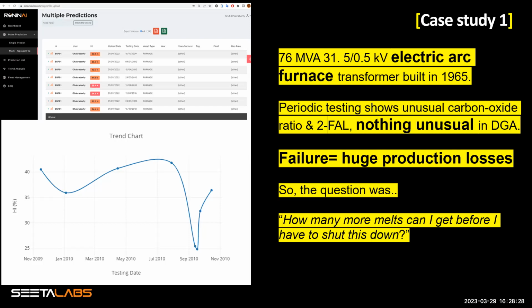For us, a health index algorithm, driven inside a machine learning framework, was basically condensing the typical condition monitoring data from that transformer, from dissolved gas analysis, oil quality parameters such as moisture content, breakdown voltage, interfacial tension, tan delta, and everything, into a number, a quantitative number, well defined inside a time scale.